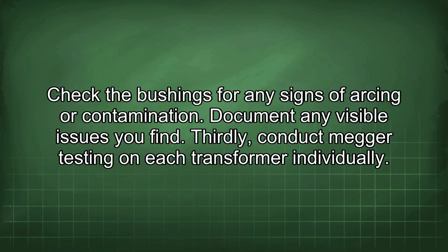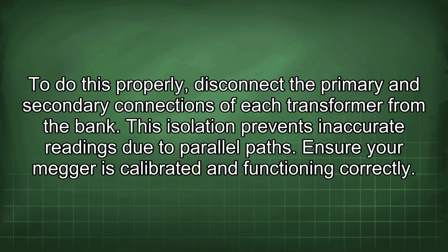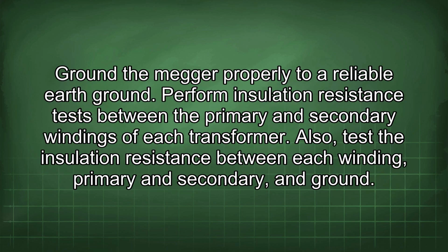Thirdly, conduct megger testing on each transformer individually. To do this properly, disconnect the primary and secondary connections of each transformer from the bank. This isolation prevents inaccurate readings due to parallel paths. Ensure your megger is calibrated and functioning correctly. Ground the megger properly to a reliable earth ground.